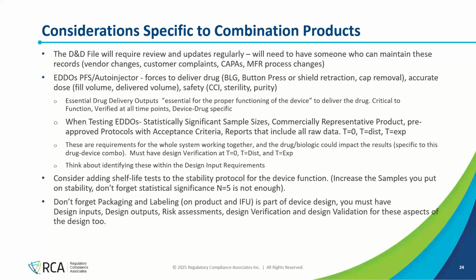EDDOs is a special thing defined by the FDA. This is called essential drug delivery outputs. These are the requirements that you define in your design inputs that are specific to this combination of drug and device, and what they define as essential for the proper functioning of the device to deliver the drug. Critical to function is another way to think of these. These are the items that you will verify at all time points. So you'll verify this at T0, straight off the end of the line or straight after sterilization. You'll verify them again after distribution, and you'll verify them again at the end of shelf life.